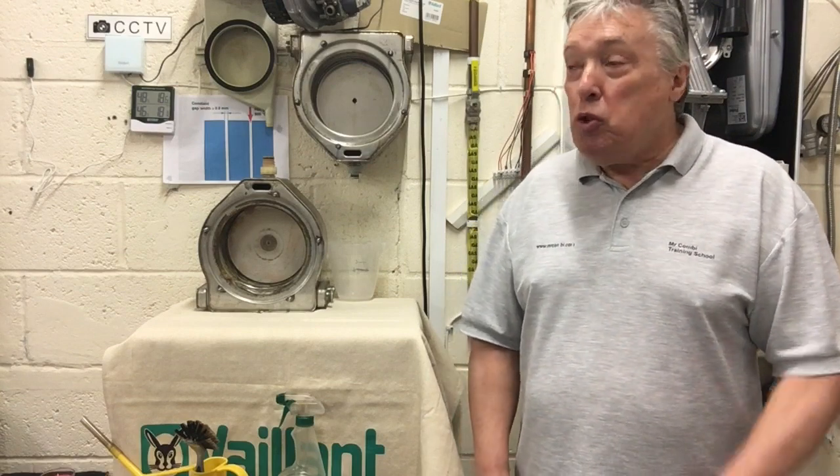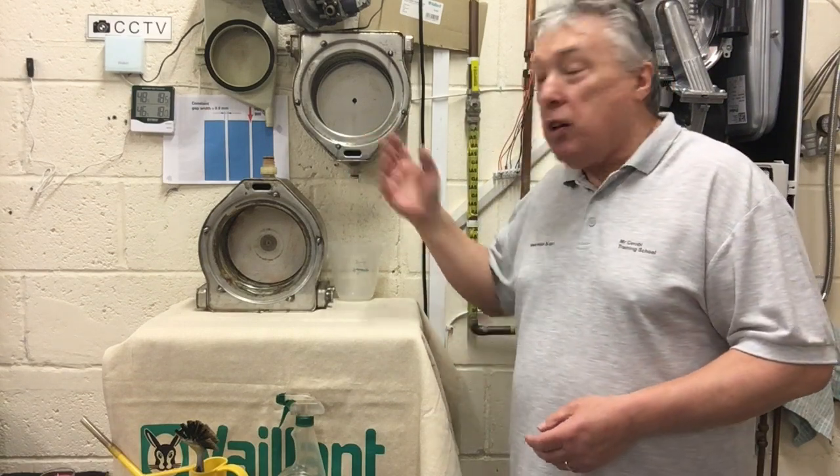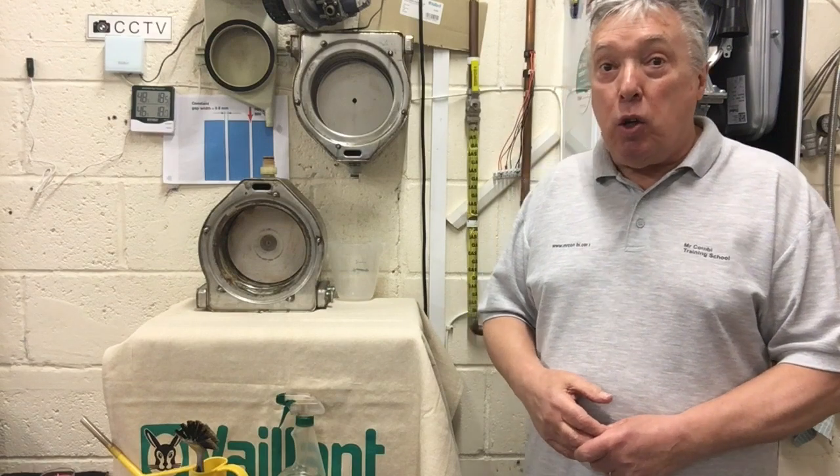I would not allow a boiler to go more than three years before I take it apart and have a look inside. The problem becomes apparent in the gaps — as you can see on the chart, it's less than one millimeter between all of these pipes, which will get blocked because the boiler is in use. You may get an error code saying your condensate pipe is blocked or the boiler has flooded, which means the gaps are blocked.